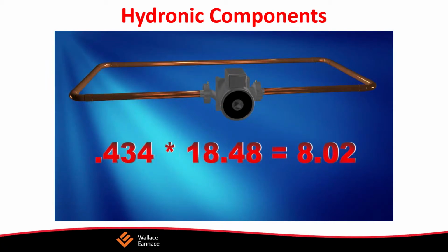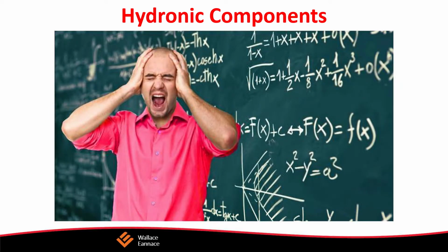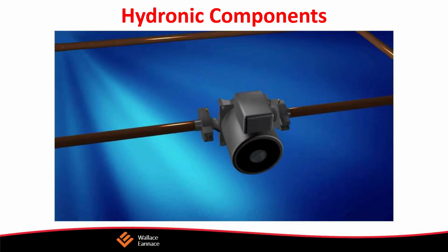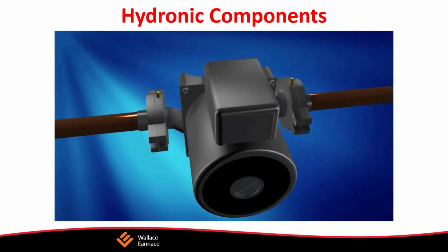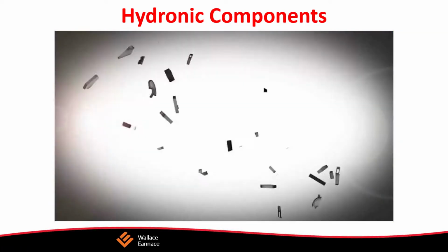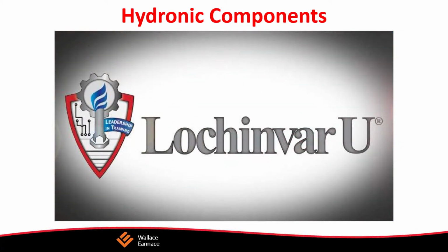The motor is the electrical device that is connected to the impeller by a shaft and is responsible for turning the impeller. It's good that we know the anatomy of a circulator when we try to understand how they work. This image represents a circulator in a closed system. Most circulators will have test ports on the suction and outlet sides of the volute. But how do I know the suction from the discharge side? There's actually a very simple method.